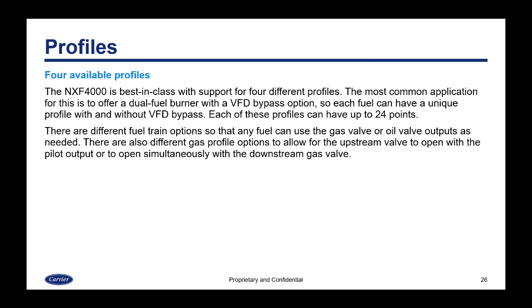There are different fuel train options so that any fuel can use the gas valve or oil valve outputs as needed. And there are different gas profile options to allow for the upstream valve to open with the pilot output or to simultaneously open with the downstream gas valve depending on your application.